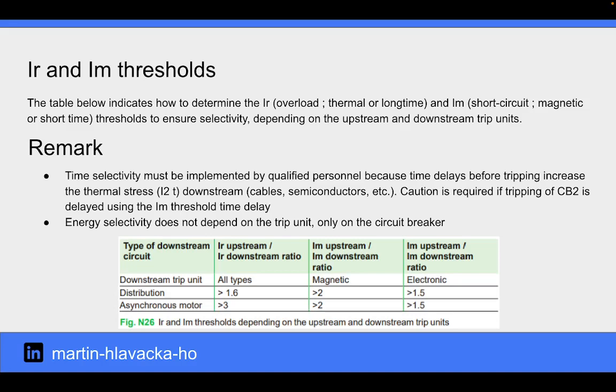The table below indicates how to determine the IR and IM thresholds to ensure selectivity depending on the upstream and downstream trip units. Time selectivity must be implemented by qualified personnel because time delays before tripping increase the thermal stress downstream. Caution is required if the tripping of circuit breaker 2 is delayed using the threshold time delay. Energy selectivity does not depend on the trip unit, only on the circuit breaker.